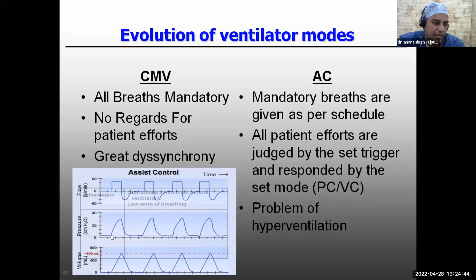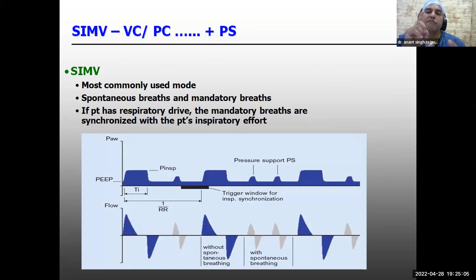Now in assist control, whenever the patient triggers, the ventilator responds with a complete full breath, by the pressure control mode or a volume control mode. Now, what does this lead to? This leads to the problem of hyperventilation. Here we have tried to show you one graph in which this is a controlled breath, but here you can see there are some triggers and this is an assisted breath, right? Then we come to SIMV mode. I think control mode is okay, and assist is where the patient triggers and the ventilator responds with the main mode. So if you say 500 ml of tidal volume is to be delivered, every time the patient triggers, 500 ml tidal volume will be given. That is assist control mode.